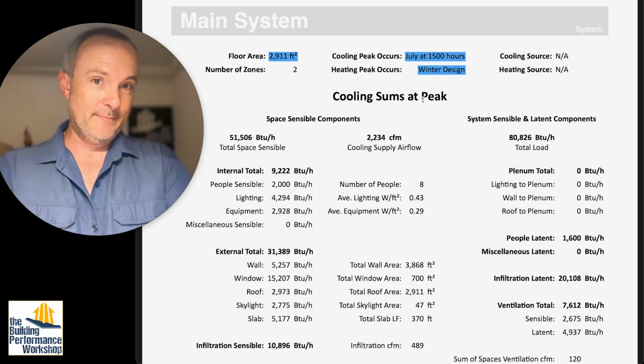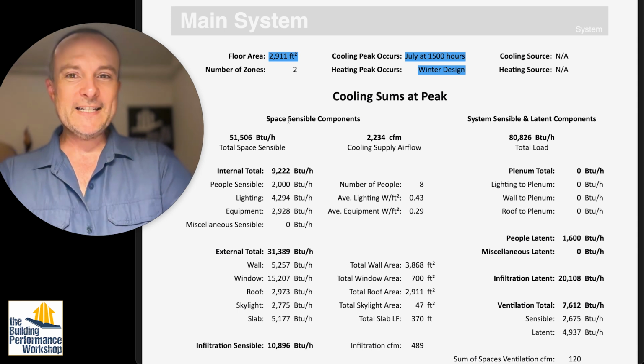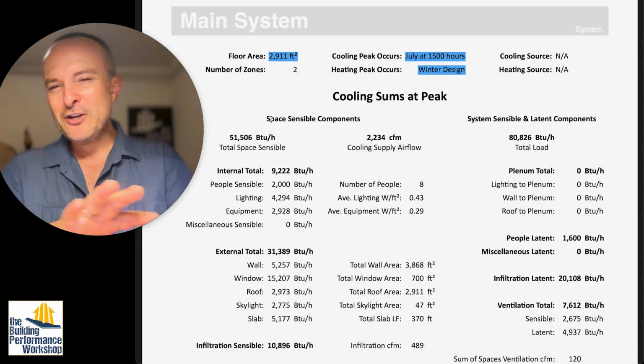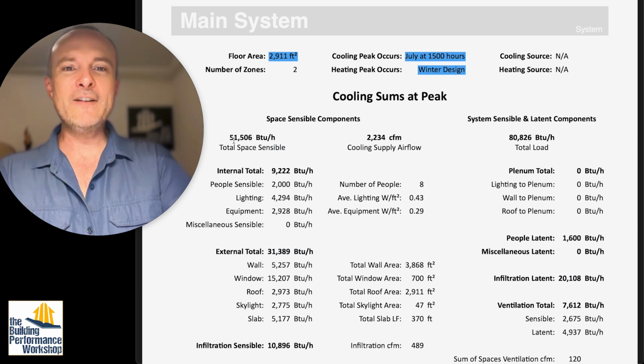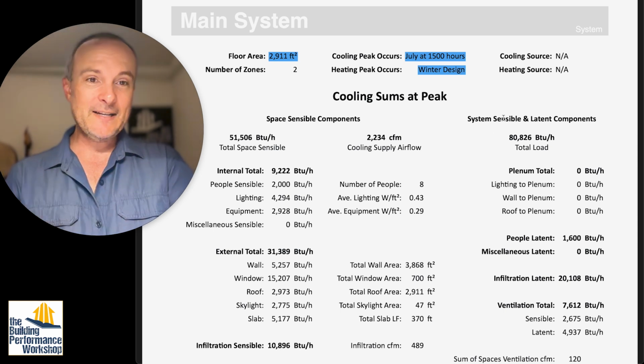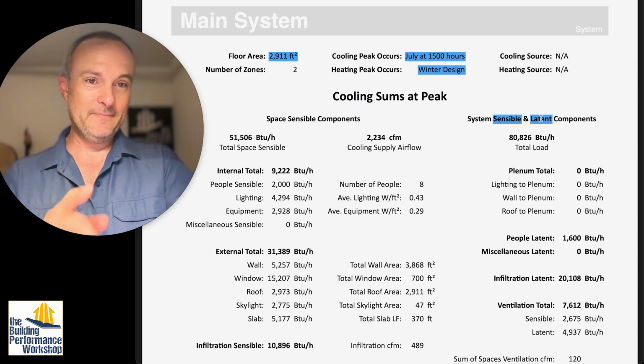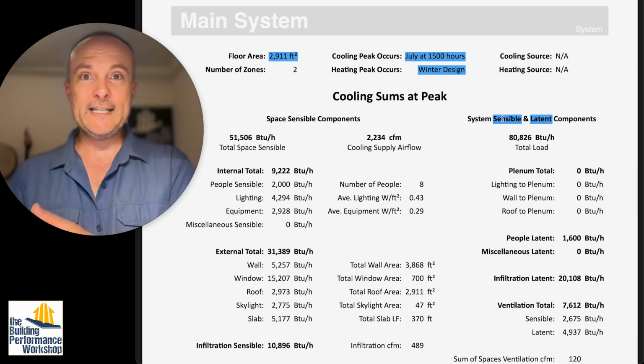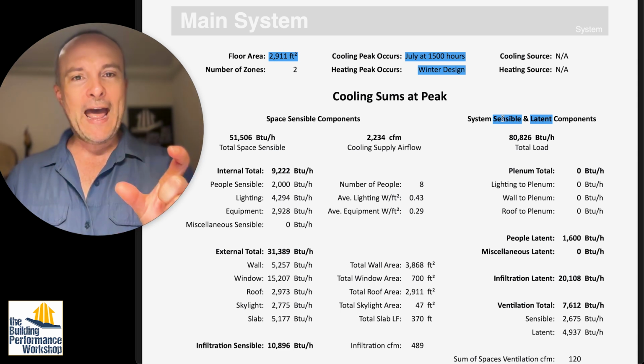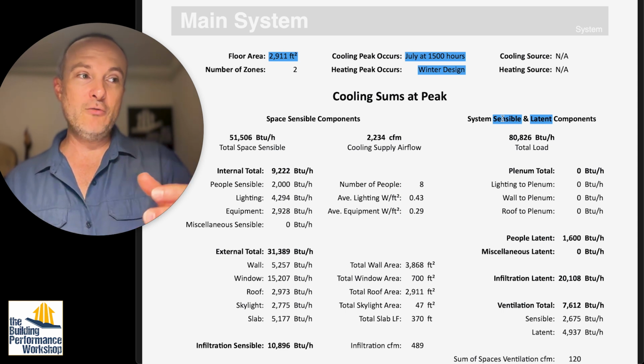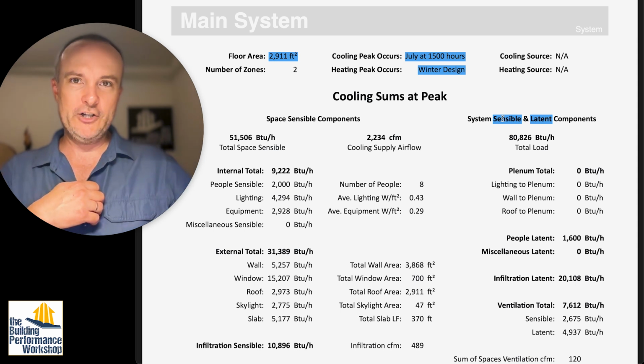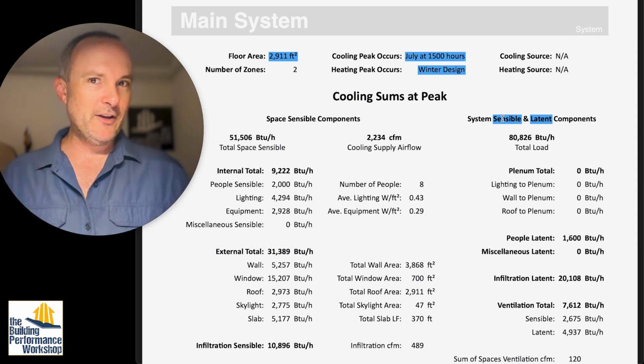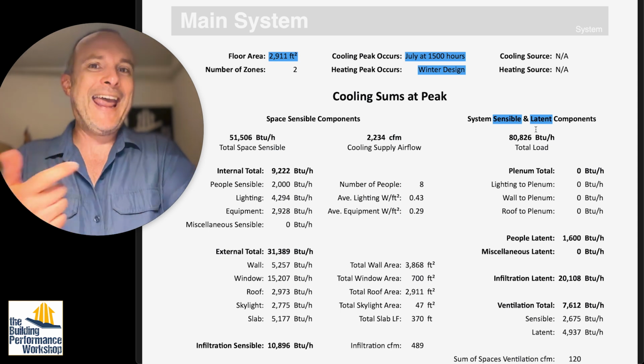Okay, so cooling sums at peak. We're just going to look at cooling for right now because it's one of the more complicated ones. You can use this same strategy with heating, but you've got two things going on in cooling. You've got sensible and you've got latent. Sensible means temperature that you can see on the thermostat. That's the actual temperature that you would measure. Latent is hidden. That's what the word means. And that is humidity. It's what happens if the humidity condenses on things, it will add more heat, just like sweating, evaporating moisture, lowers the temperature. That's why you sweat. The latent heat is something that can add to the heat inside the house.